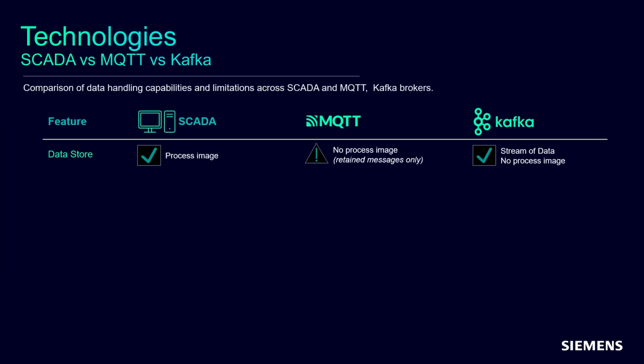Regarding data store, in a SCADA system we typically have a process image where we store and know the last and current state of the tags, topics, and data points. In MQTT this is out of the box not the case: if you don't use retained messages, the broker only passes messages by without storing the last value, so there's no way to read the last well-known state of a topic. In Apache Kafka it's the same as MQTT -- there's no way to get the latest current state of a topic, because we always have the stream of data.